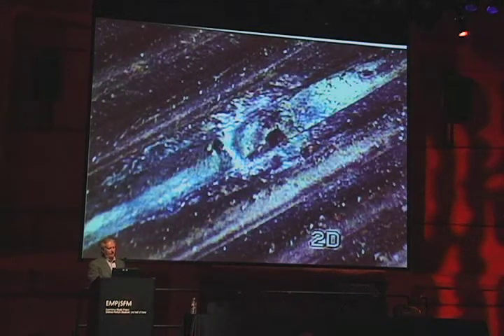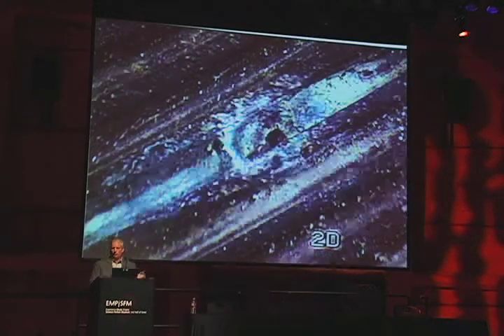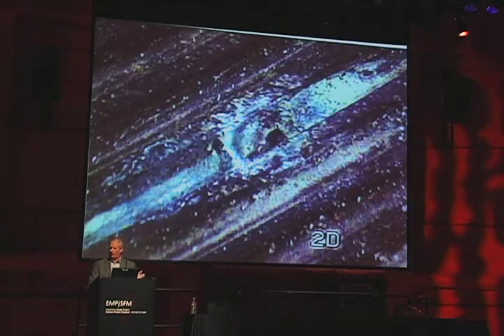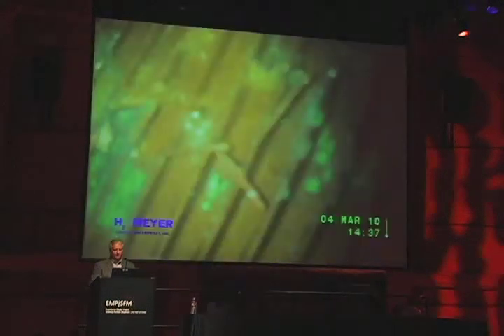Here we actually found a hole in the tube itself. It actually pitted through the tube right there, allowing water to get into the Freon side, and water and Freon don't mix very well. It's a very aggressive combination. It causes rapid corrosion inside the chiller. So this cost about $100,000 to replace and retrofit this chiller because of the pitting that occurred on the tube surface itself.